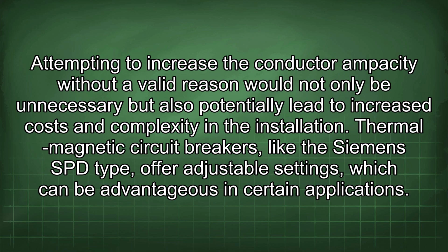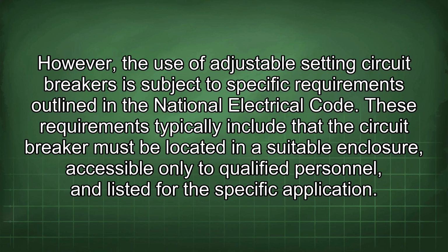Thermal magnetic circuit breakers, like the Siemens SPD type, offer adjustable settings which can be advantageous in certain applications. However, the use of adjustable setting circuit breakers is subject to specific requirements outlined in the National Electrical Code. These requirements typically include that the circuit breaker must be located in a suitable enclosure, accessible only to qualified personnel, and listed for the specific application.